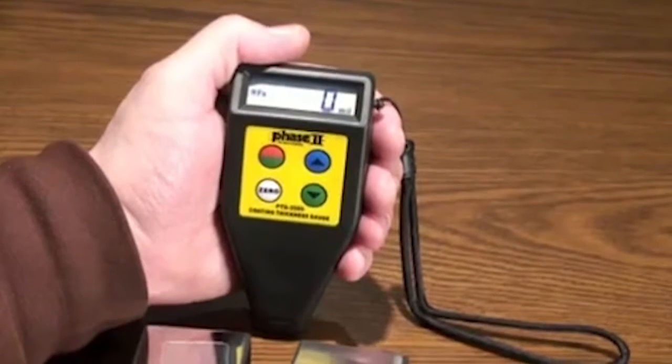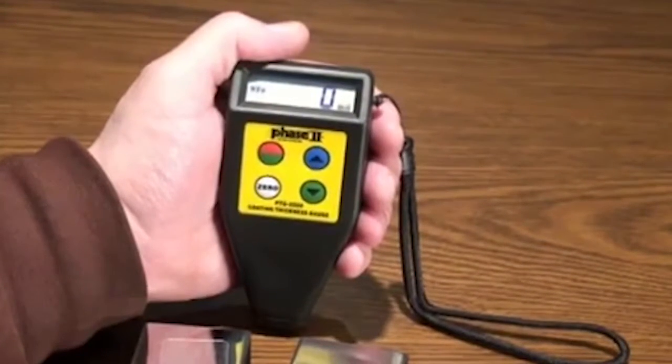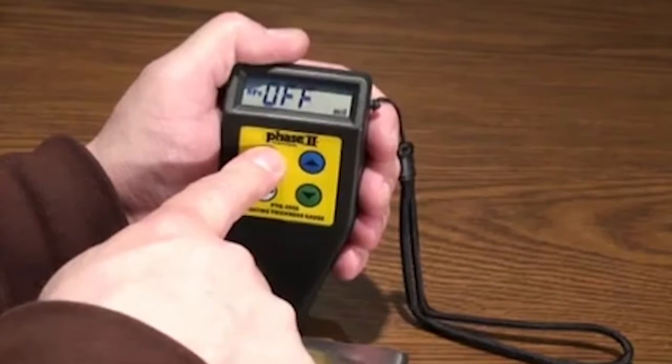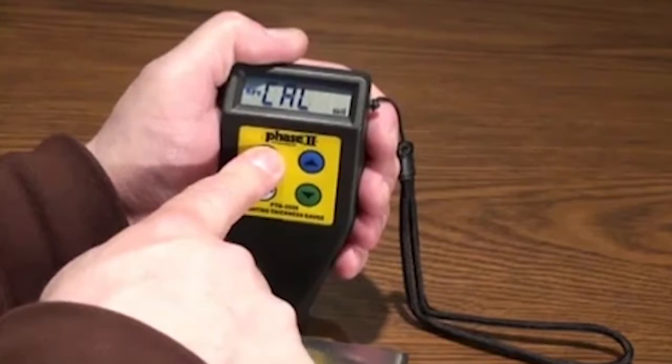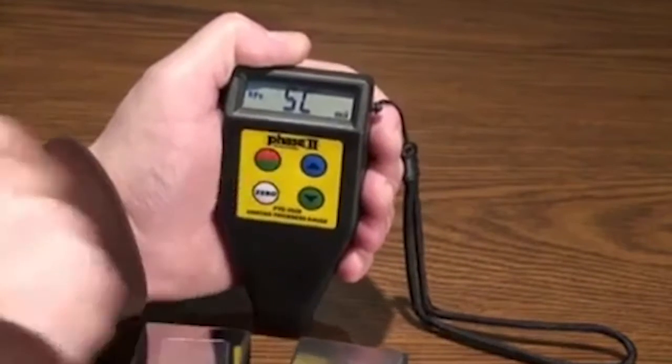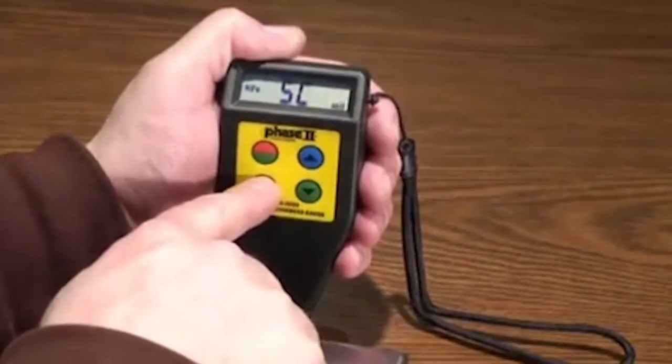To change from single measurement mode to continuous scan mode, hold power key down approximately 9 seconds until SC is displayed on the screen. Immediately press the zero key to set to next mode.